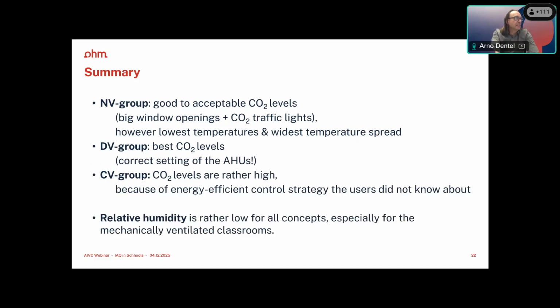And the summary of that is that the natural ventilated group has good to acceptable CO2 levels. They have big windows with sliding ones, and they have CO2 traffic lights. However, they also have the lowest temperature and the widest temperature spread regarding the room temperature. The decentralized ventilation group has the best CO2 levels when the setting of the AHU is correct, and the centralized ventilation group has CO2 levels that are rather high because of an energy efficient control strategy that the users didn't know about. And we saw in all concepts that the relative humidity is rather low, and it was especially low for the mechanically ventilated classrooms.